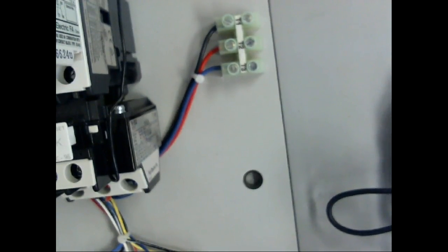So if I come over here, I know it's not being recorded. This is a control relay. So it's got the symbol of the coil. It says my coil is between number 13 and 14. Which one goes to L1? Which one points straight up? It's just a relay coil, right? It don't make any difference what goes to L1 or L2, but I know there's my manufacturer number. This says I have a normally open contact between 12 and 8, and I have a normally closed contact between 12 and 4. Because it's a single pole double throw switch.